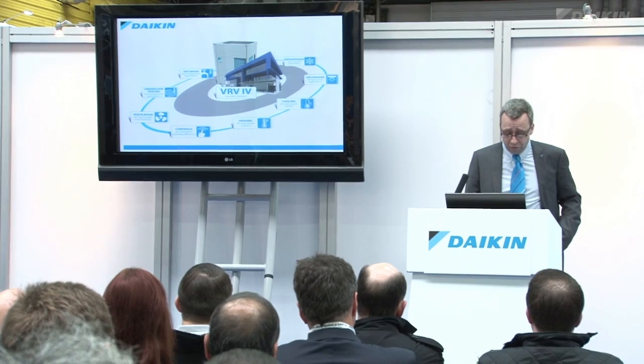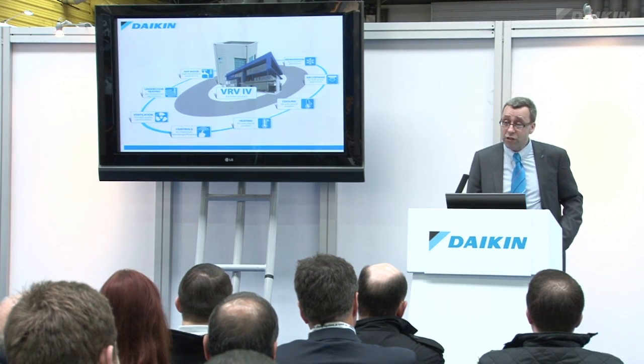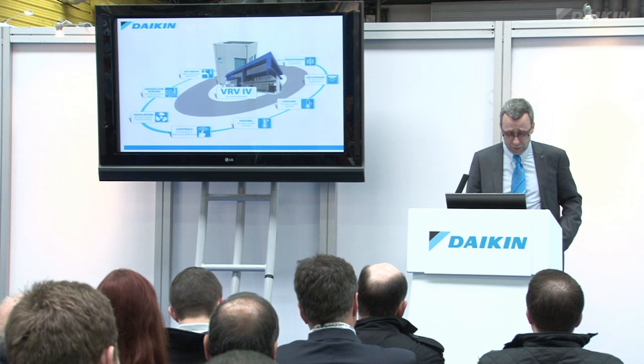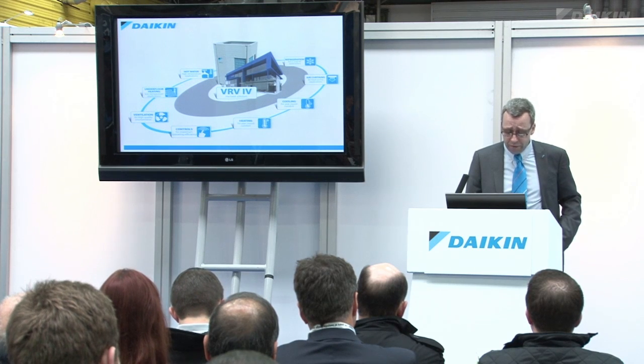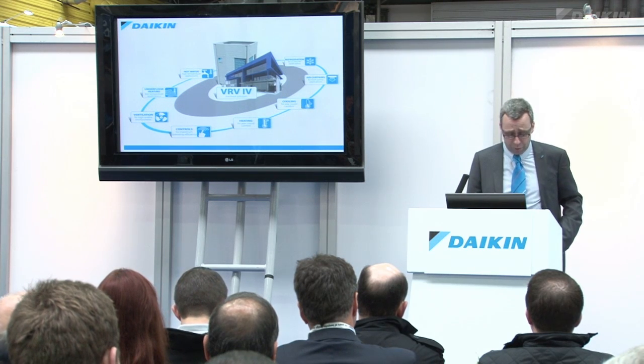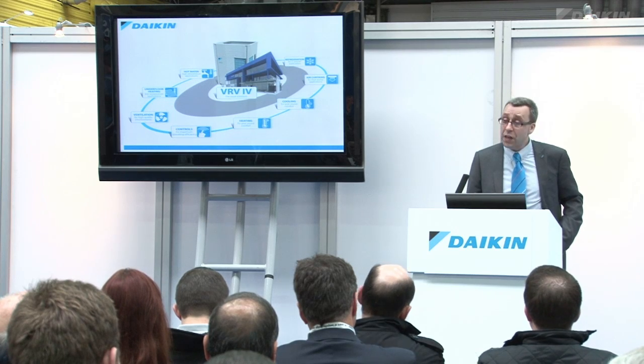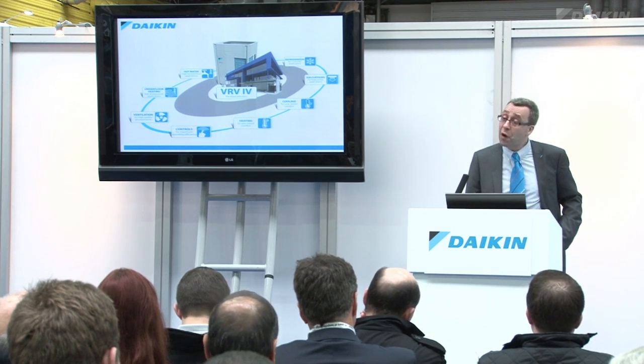By showing you the results of a real installation, where a VRV3 system was installed and monitored, not by us, but by the customer. And then we swapped a condenser for a VRV4 system with variable refrigerant temperature. And the results were quite astonishing. What was shown was that VRV3 already had the best performance on the market, but this has now been surpassed, and not just by a little bit.